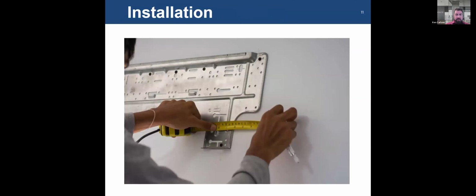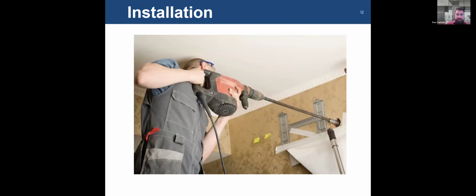Typically the indoor units all have a mounting bracket. On that mounting bracket, there are indications as to how to line up your center line for your hole. Typically you'll utilize one hole. In that penetration, you'll go from your interior wall to the exterior wall, and all your refrigerant lines, your drain, your power and communication lines all go through that same penetration. This photo is a little overkill, but one thing to note when you are drilling through a wall, whatever the material may be, is to keep a pitch going down. That is for the drain line itself. We want to make sure that the condensate can go downhill and actually leaves the pan and goes to the next point.